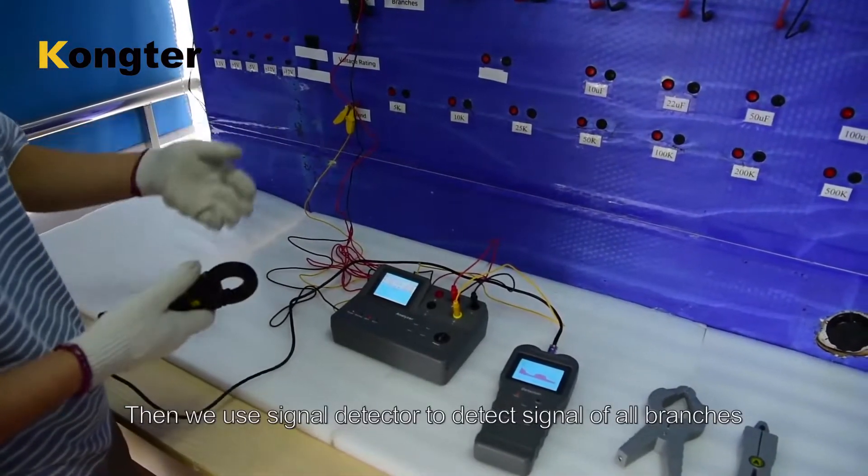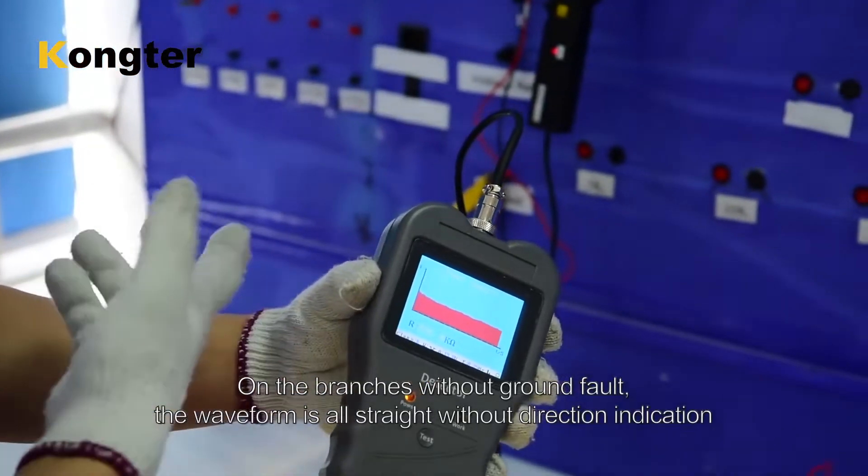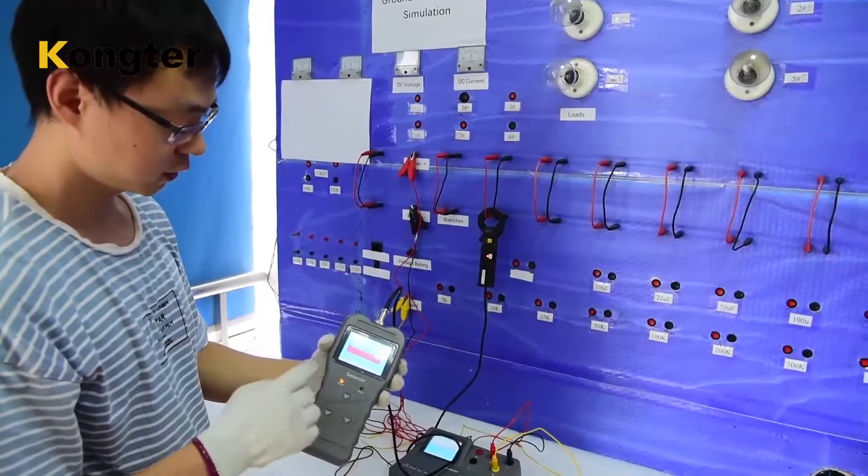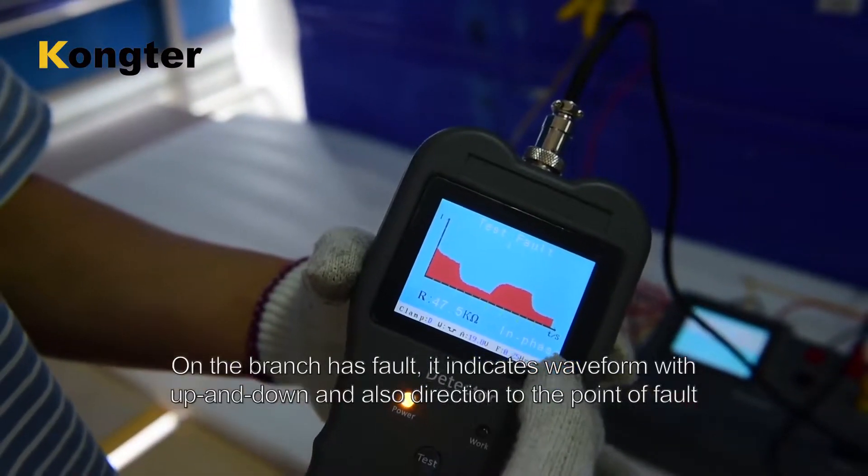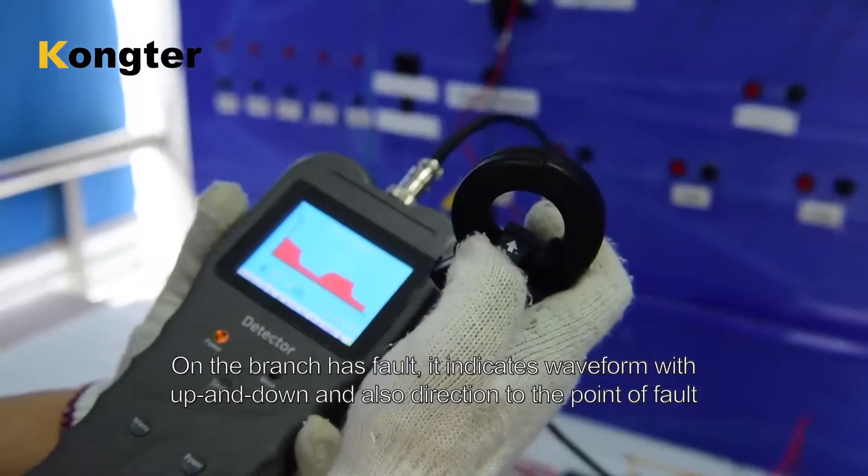Then we use signal detector to detect signal of all branches. On the branches without ground fault, the waveform is all straight without direction indication. On the branch with fault, it indicates waveform with up and down, and also direction to the point of fault.